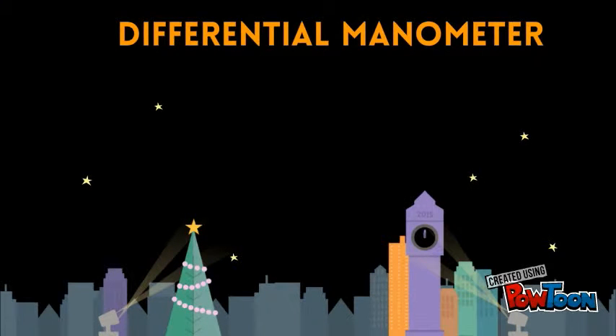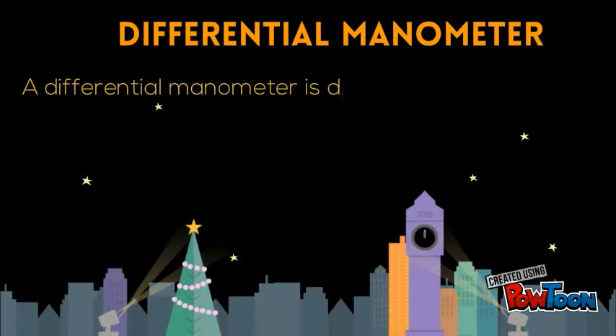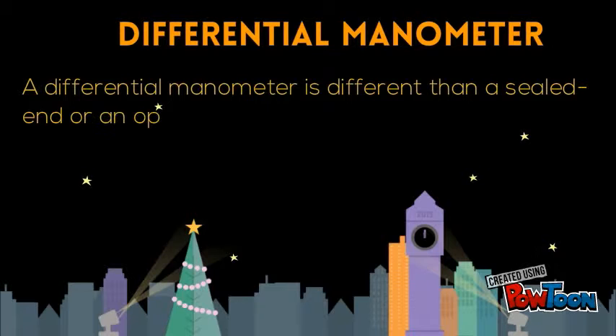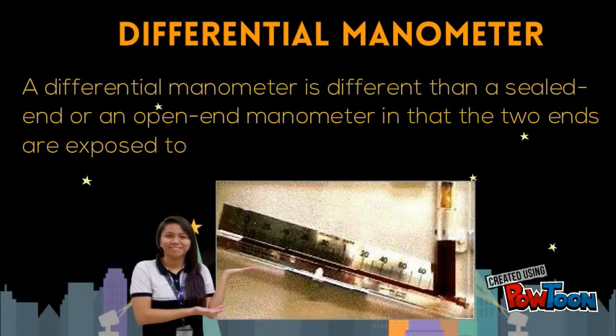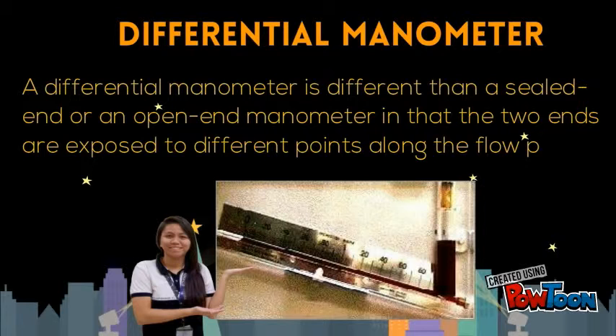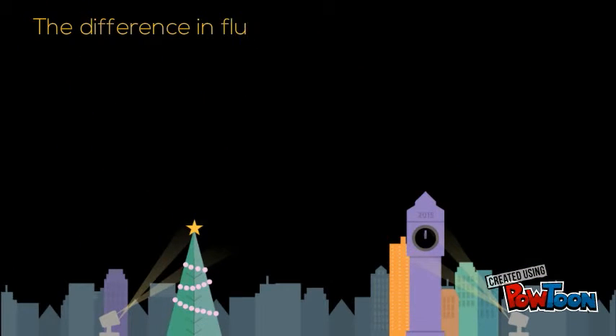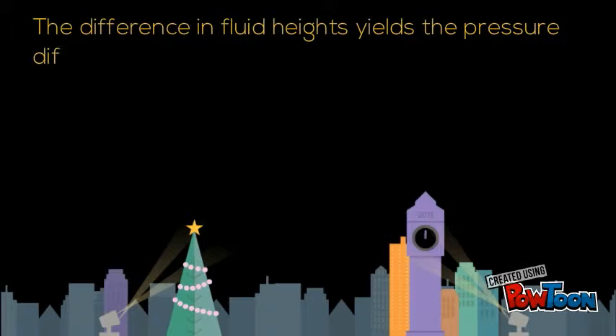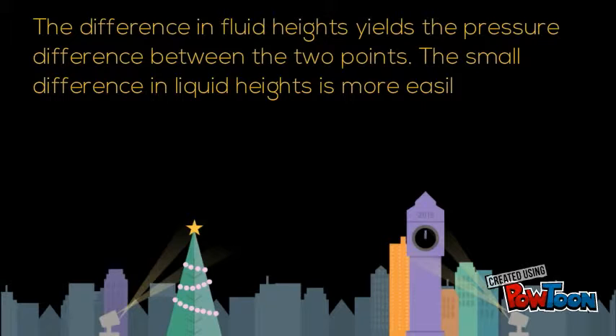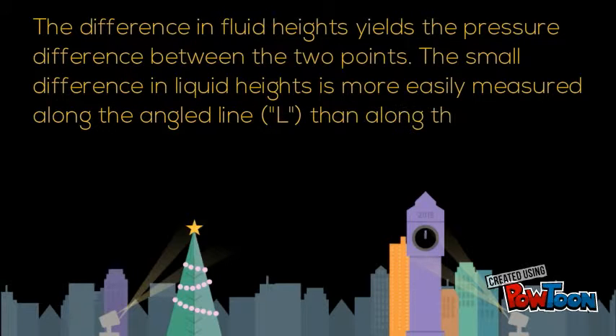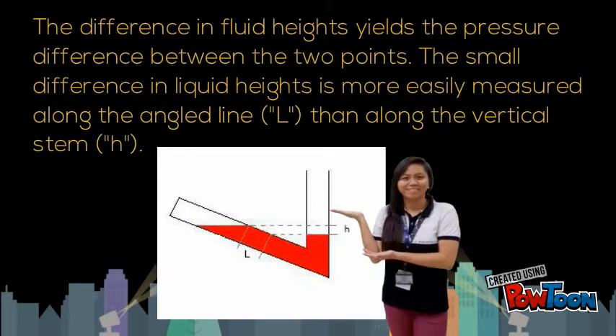A differential manometer differs from a sealed end or open end manometer in that both ends are exposed to different points along the flow path. The difference in fluid heights yields the pressure difference between the two points. The small difference in liquid heights is more easily measured along the angled line than along the vertical stem.